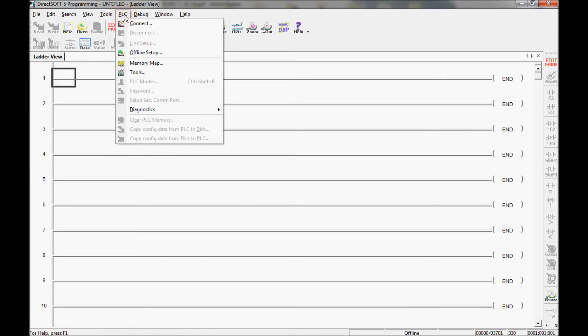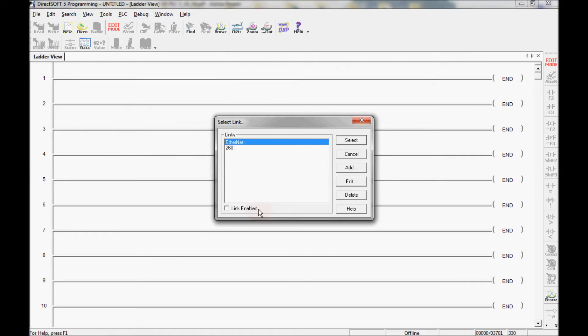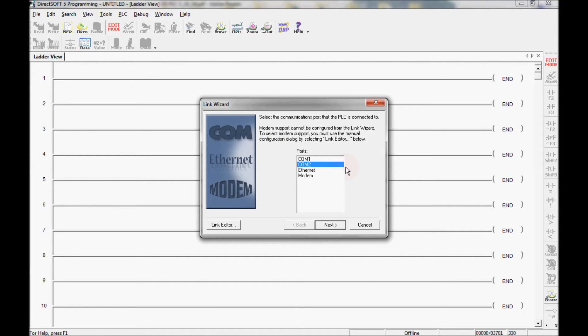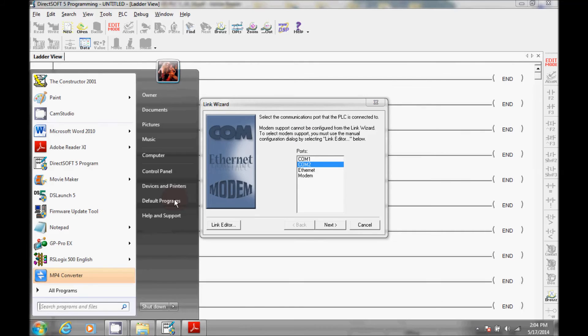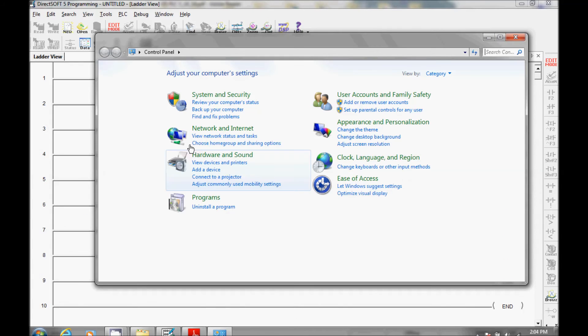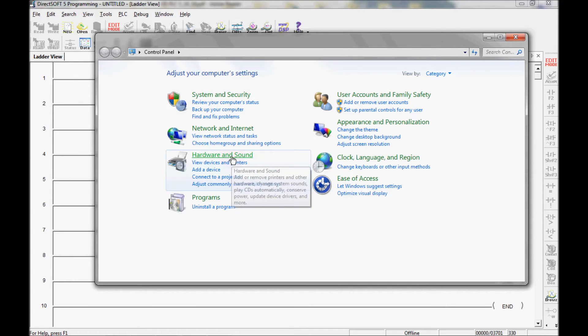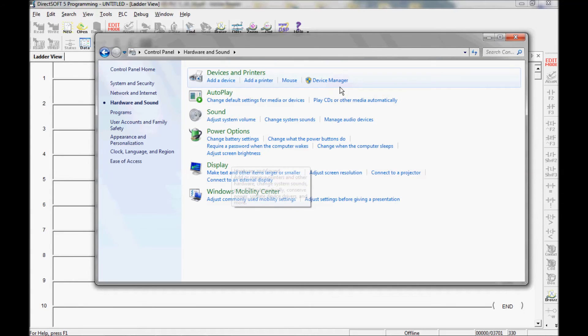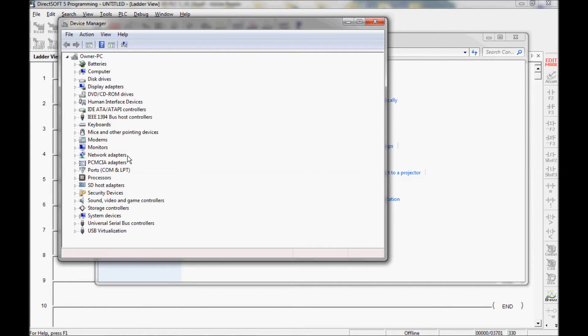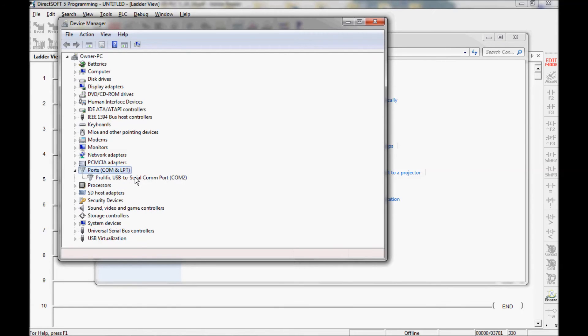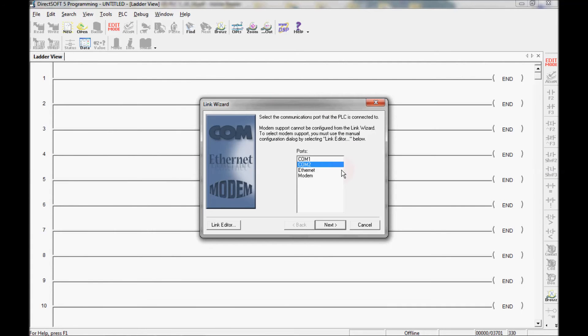I'm going to come here to the PLC and then connect. The select link window opens up and as I can see there are no links for a 330 or 305 PLC here. So I'm going to add a link here. Now I can either use the link editor or I can use the wizard itself. The wizard is asking me which COM port do I have my programming cable plugged into. If you need to find which port you're connected to, you can come here to control panel, hardware and sounds, device manager and it brings up the port section here and you can see I'm connected to COM port 2 with my cable.